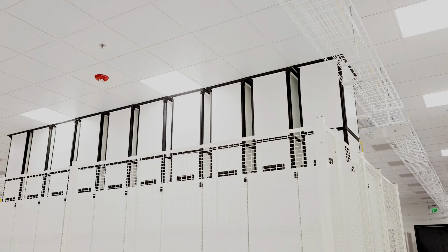This controls the flow of hot air and forces it into the plenum so it can't mix with the cold air in the room. Our chimney cabinets support a minimum of 17 kW to over 30 kW actual load depending on the equipment installed. DataBank has tested this design to 34 kW of actual load utilizing load banks and real-world testing. We do have the capability of doing 100 kW per cabinet by utilizing water-cooled backdoor configurations.